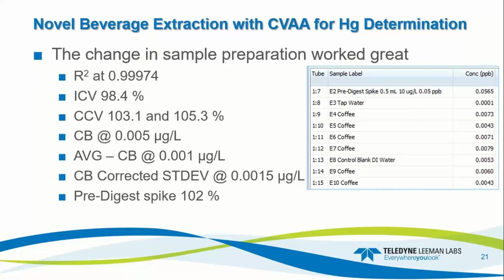So the change in preparation worked great. R squared was 0.99974. My initial calibration verification was 98.4. Continuing was 103 and 105. The control blank came in at 5 ppt, 0.005 ppb, and the average of the samples minus the control blank was 0.001. So now we're basically down to the non-detect level, which was hopeful, and I drink a lot of coffee, so that's all good.